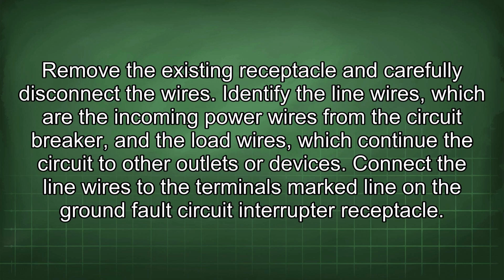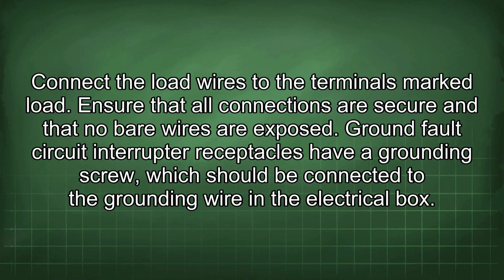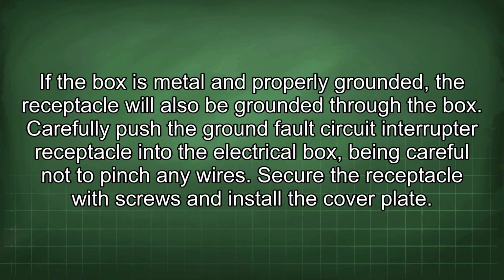Connect the line wires to the terminals marked line on the ground fault circuit interrupter receptacle. Connect the load wires to the terminals marked load. Ensure that all connections are secure and that no bare wires are exposed. Ground fault circuit interrupter receptacles have a grounding screw, which should be connected to the grounding wire in the electrical box. If the box is metal and properly grounded, the receptacle will also be grounded through the box.